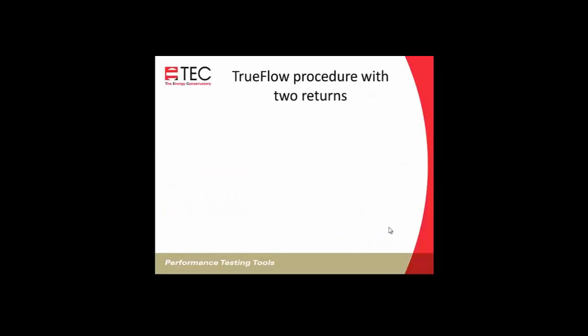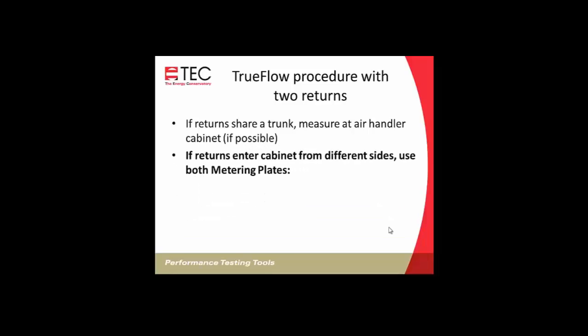So, procedure using two returns. If the returns share a trunk, we can measure right at the air handler inside the cabinet if possible, or if there's a filter rack there, we can measure it at that location. The TrueFlow plate can be put at an angle in a filter grill, or in a return drop, or a filter grill. It can be put at an angle as long as it's not 2 inches away from an obstruction downstream or 6 inches upstream. We can put it in at an angle.